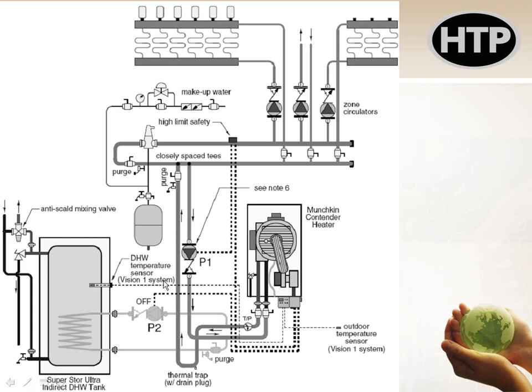And you can see I have two pumps in this case, P1 and P2. Both of them are controlled by this boiler. What this boiler can do is look at a sensor that we install in that domestic water tank, and say we set it up for 160 degree water, and we see the water temp drop to, say, 140. We say, okay, we need to heat up the domestic water. I'm going to shut off pump 1 and stop heating the house or the building, turn on pump 2 and heat up the domestic water, and then it'll take, say, 10 minutes, for example. And then when that's satisfied, I'll turn pump 2 back off and go back over to pump number 1, heat the building again.